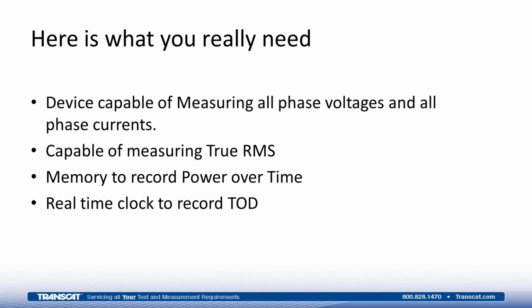Now, typically to do this type of recording over time in order to calculate the energy, you would have to have memory in the instrument. It would have to be capable of recording this information and giving it back to you at a subsequent time, telling you how much was being used instantaneously, which is, again, the power, but then looking at the energy usage over time, which would be the watt hours of information, or var hours or VA hours.